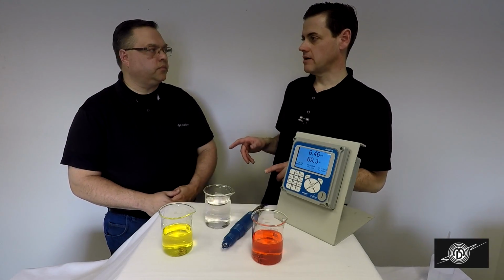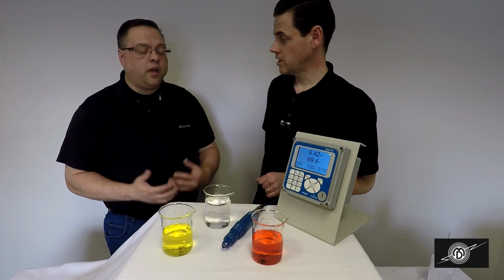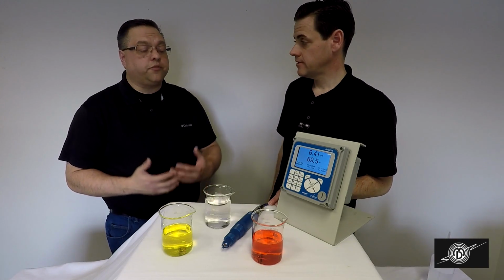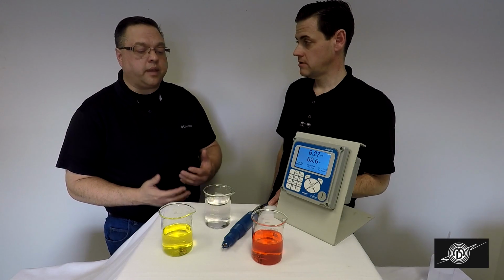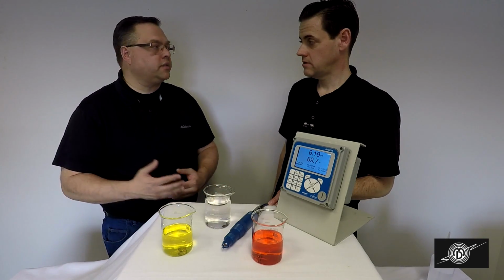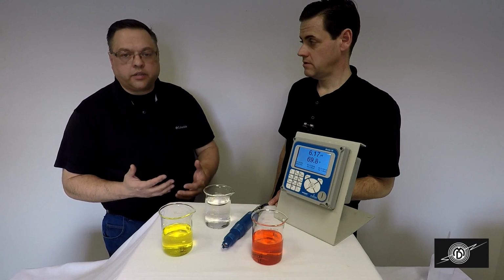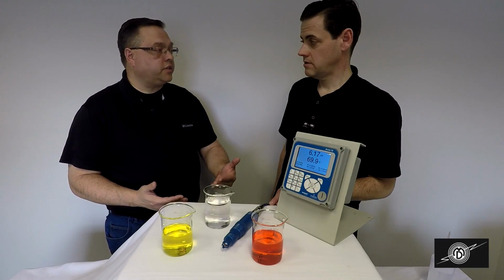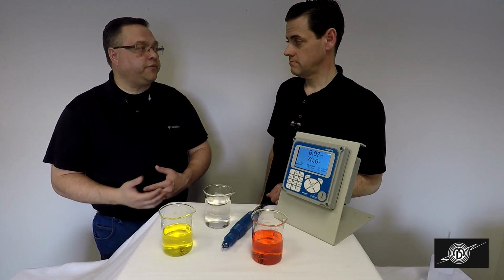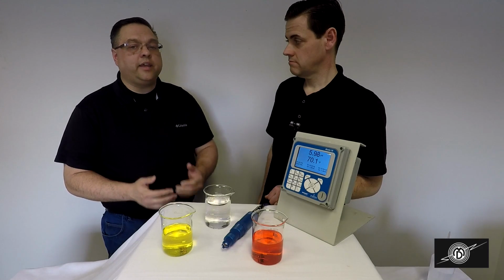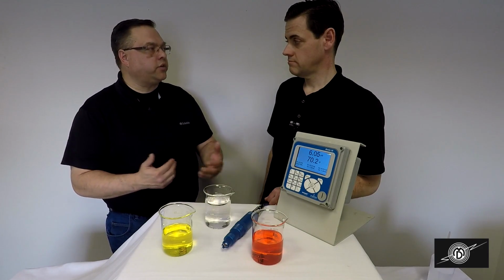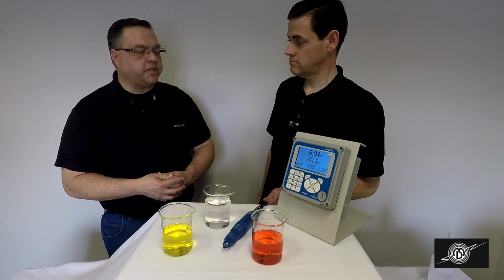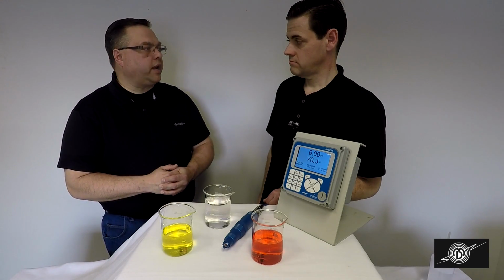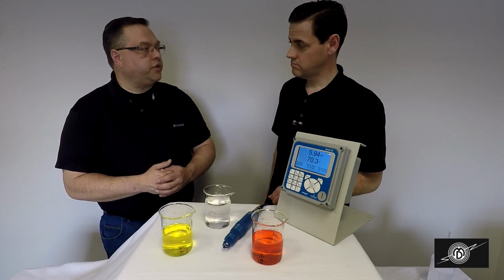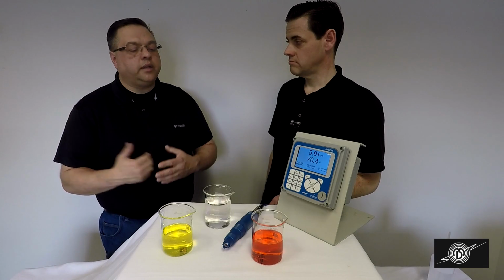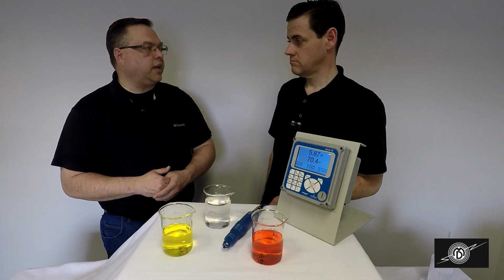And now I got a question for you, Mark. How often should we calibrate a system? I recommend that when you first get it, you calibrate your pH system, then check it at least once a week. That means pull the probe out, clean, rinse it, and place it in 7 buffer. If it's plus or minus 1/10 of a pH unit, you know that it's still stable and move on. If it's more than a few tenths away from your pH 7 buffer, then you'll need to recalibrate. If it takes a week or two before it starts drifting more than a few tenths from 7, now you'll know how often your calibration procedure will be. So you can expand it to once every 2 weeks. Maybe it becomes once a month. But to start with, start once a week, at least just checking it, and then go from there.